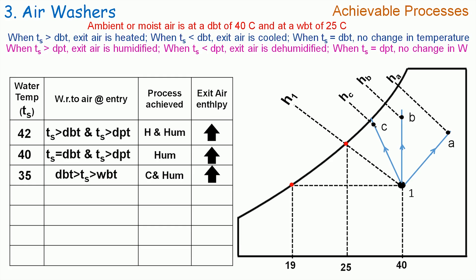Let us now make the spray water temperature to be 25°C. Here TS is less than the dry bulb temperature, hence air is cooled. And TS is greater than dew point temperature, hence the air is humidified. Therefore, the achievable process by the air washer is cooling and humidification. But please note that in this case TS is equal to wet bulb temperature. If we plot it on the psychrometric chart, then process 1D will be representing it. The enthalpy HD is equal to H1, hence exit air enthalpy remains constant during this process.